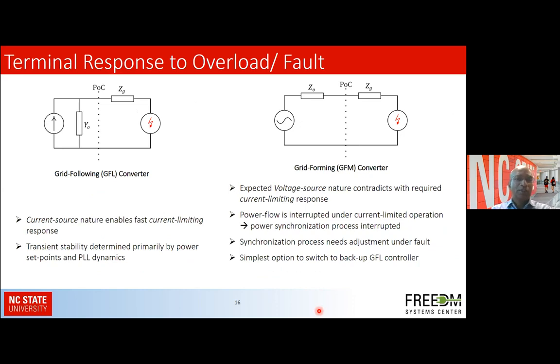For grid following converters, I'll talk a little bit about some of the characteristic differences in terms of the different controllers for these two types. The grid following converters are current source in nature, enabling fast current limiting response. And the transient stability is determined primarily by the power set points and the PLL dynamics. But the GFM inverter, which has to do voltage tracking also, the expected voltage source nature actually contradicts that current limiting response. And if you have to go into an alternative method under fault modes, then, for example, it could go into current limited operation. The power synchronization process itself gets interrupted. So the synchronization process needs to adjust under fault, and that's why the simplest option has been to switch into a GFL type converter under faults.